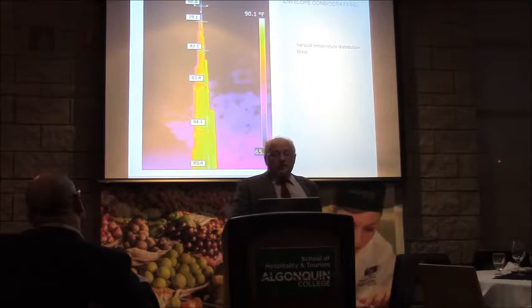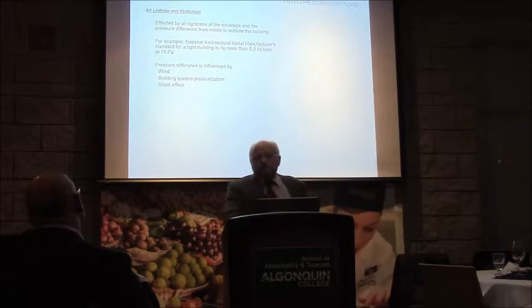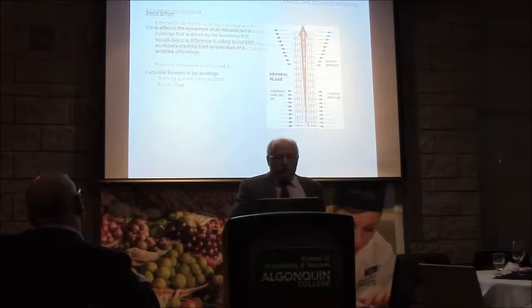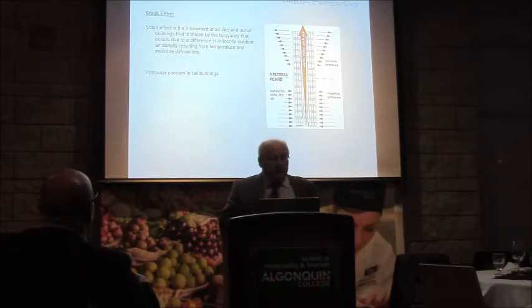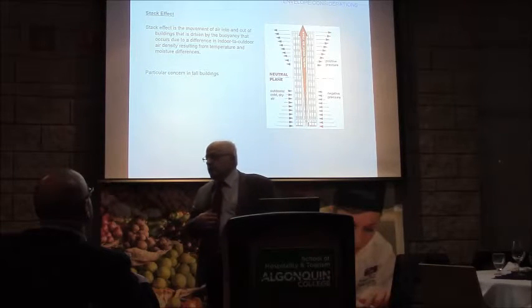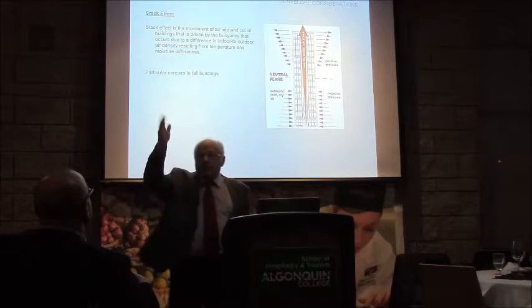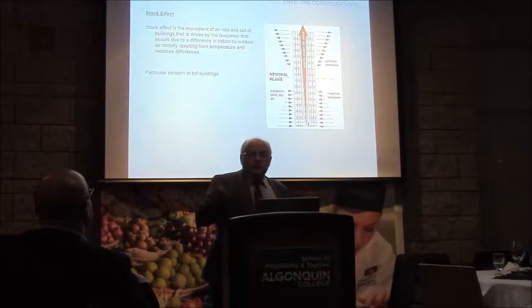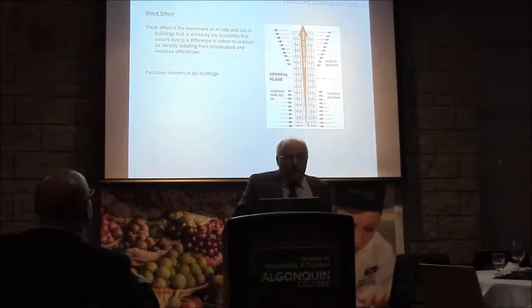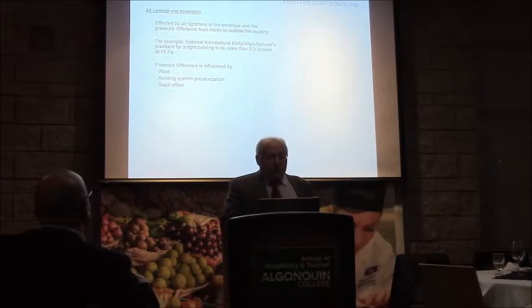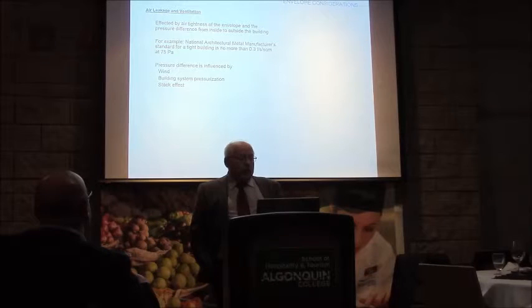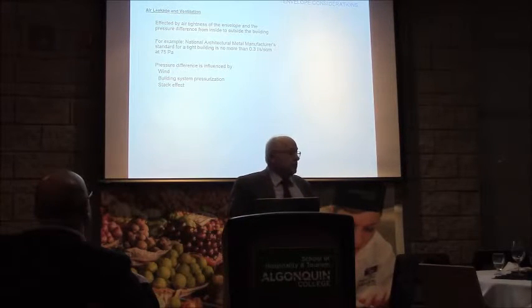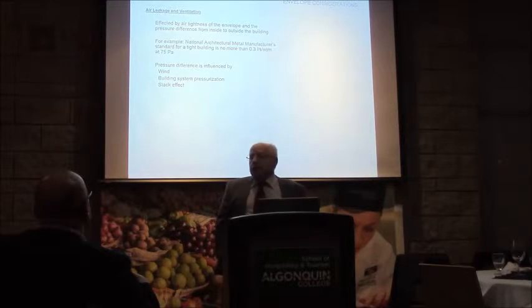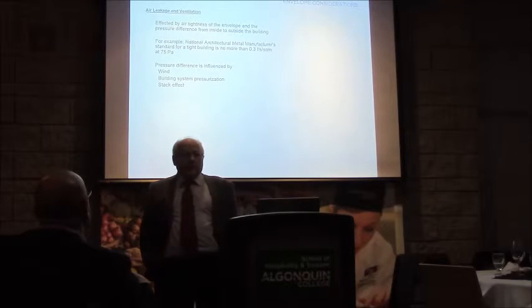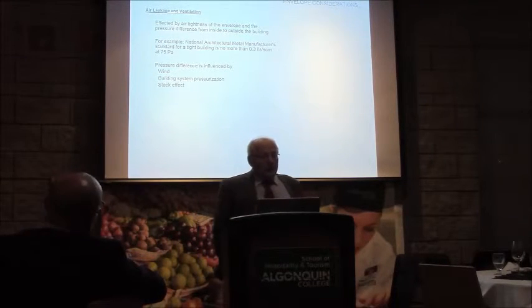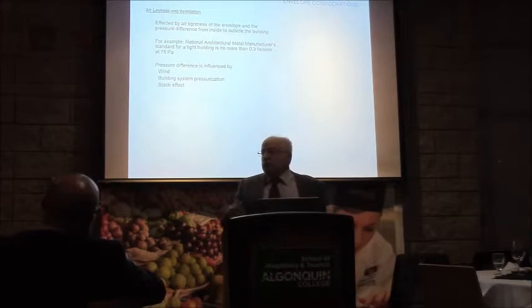As a direct consequence of being a tall building, we have a major issue typically with stack effect. For us in winter, stack effect means air rushing in the bottom and out the top. In summer, in more extreme conditions, it's reversed - air comes in at the top and rushes out the bottom. The envelope, which is supposed to have such good tightness qualities, is important for controlling that. But also things like sealing up mechanical areas, closing off elevator shafts, the top of the elevator shaft, building pressurization - all these things have to be considered to control that kind of problem.